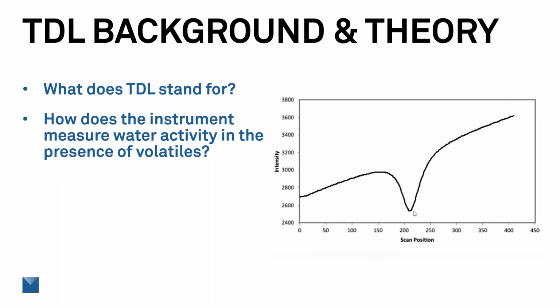So you can see it operates over a fairly narrow bandwidth. We don't have nanometers listed on here. We just have a scan position. But this entire range is going from about 1830 to 1840 nanometers. And so we're able to really pinpoint that water absorption peak in a way that it isn't influenced by other volatile containing compounds. And who needs this technology, and what market segments are we currently serving with it?